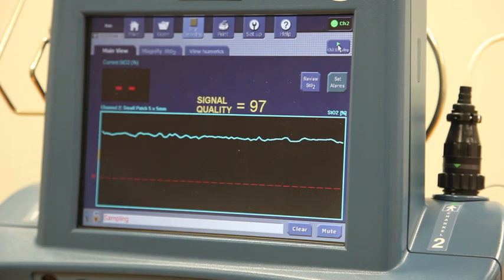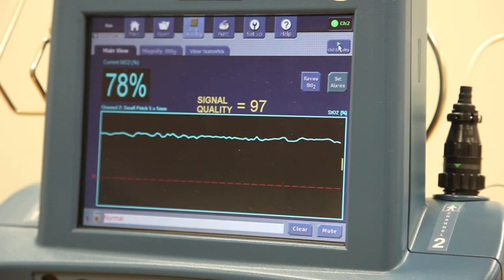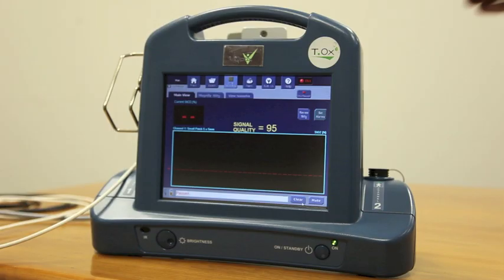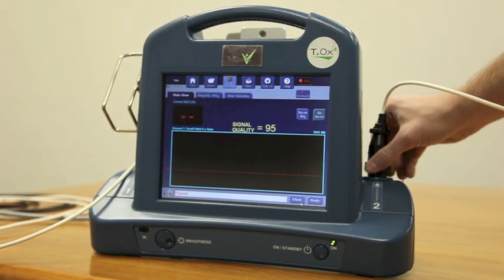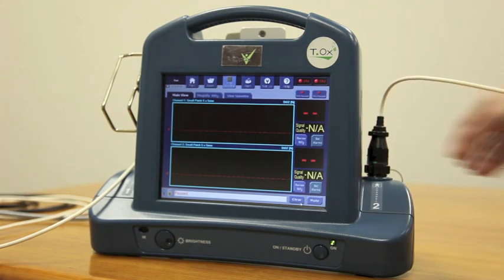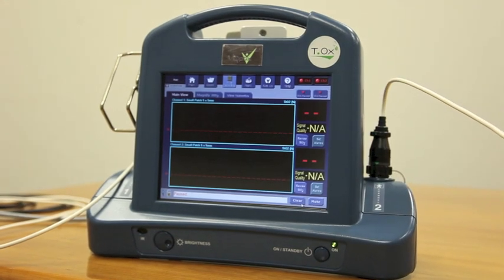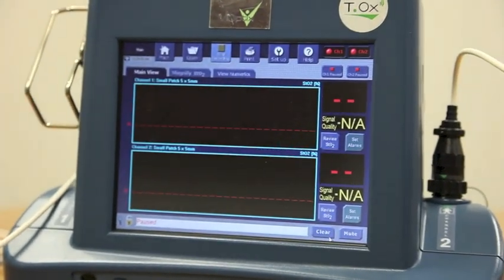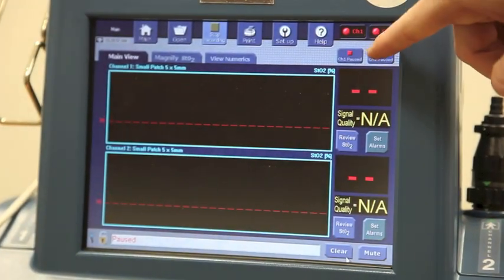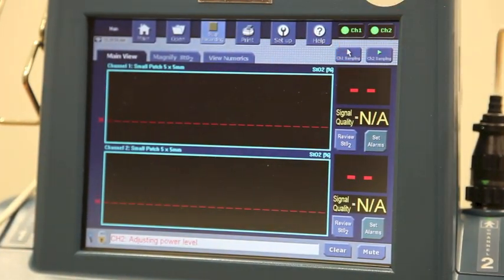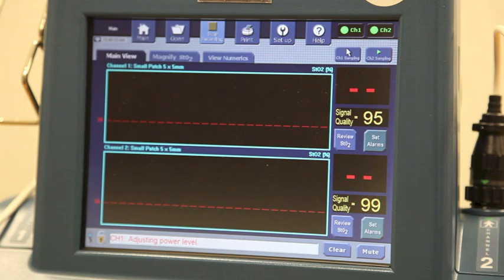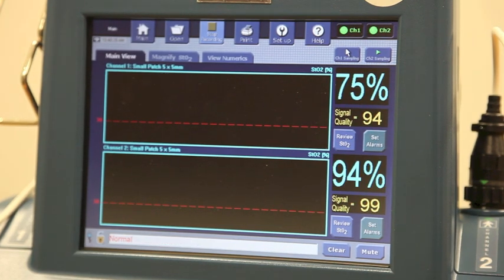This data is also displayed in a trend graph format, which indicates where the readings fall with regard to the lower alarm settings. Keep in mind, ViOptix measures oxygen locally and continuously, which will provide a different number than a pulse oximeter. When applying the second sensor, notice the change to the user interface. A second red square appears, so each channel will be able to start and stop independent of one another. Notice the screen is now split, giving the users 2 trend lines, signal quality readings, and StO2 percentages.